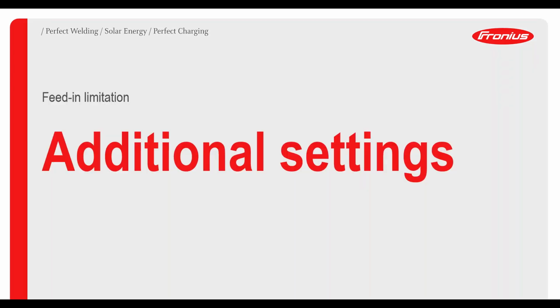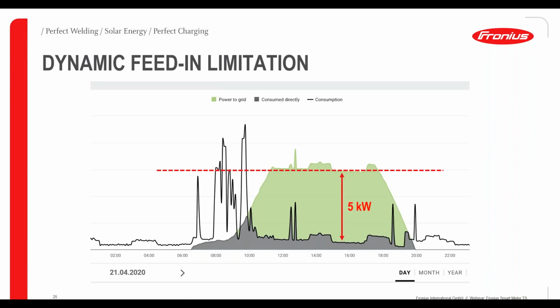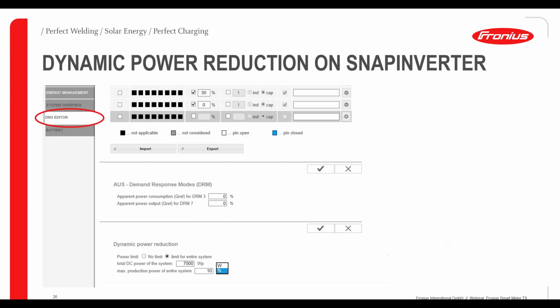All right, there are some additional settings on the web interface of the inverter when we have a smart meter installed, and that's the dynamic feed-in limitation. So you can simply limit your feed-in amount to the grid. How you do it: once you're connected to the Wi-Fi of the inverter, you go to the web interface of the inverter. In this case, this is the Snap inverter. Then under Settings, in the sub-menu DNO editor, you have the dynamic power reduction, for example. And here you choose limit for the entire system.